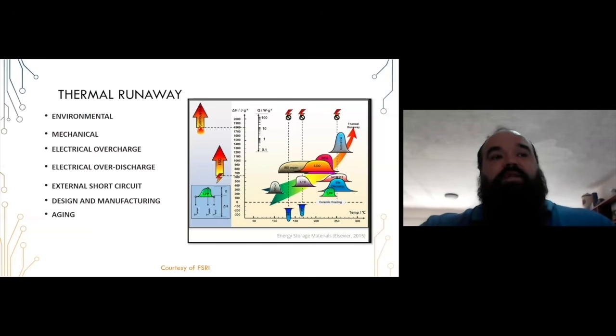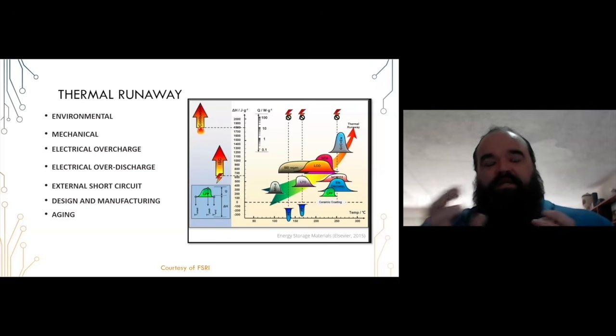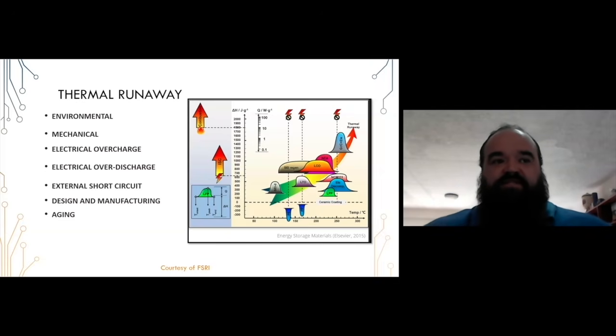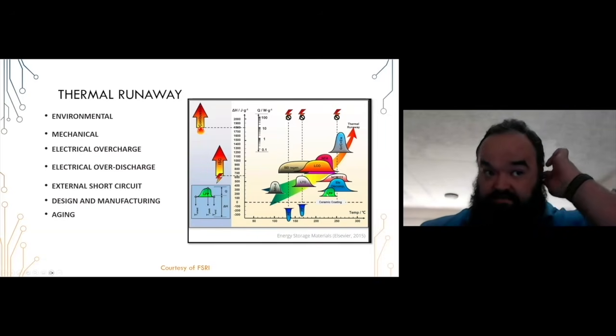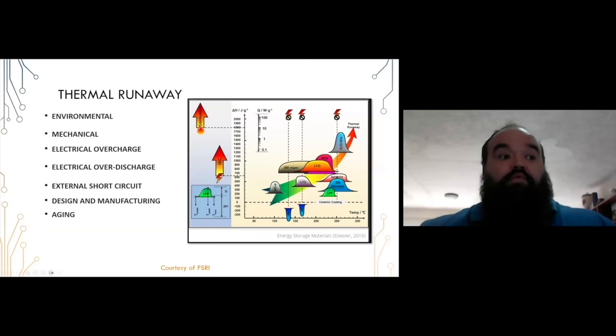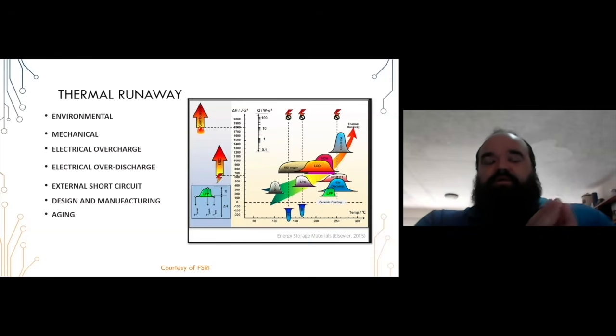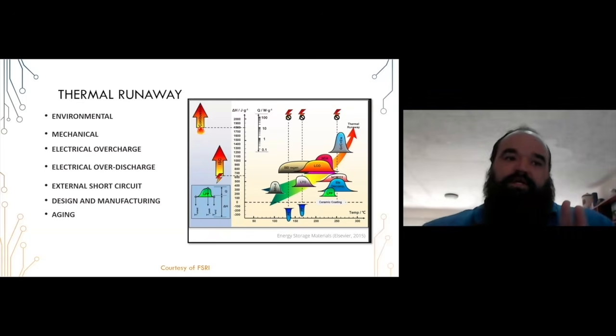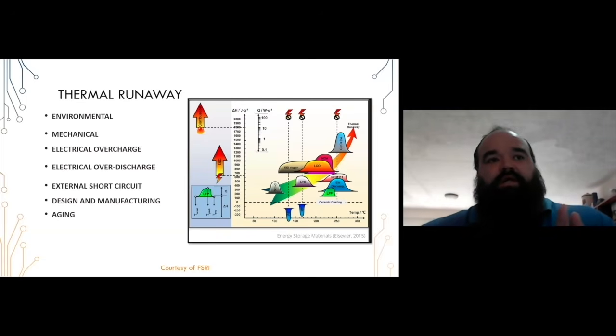Now, thermal runaway is typically caused by a couple of various techniques, and thermal runaway variances differ on the makeup of the battery. Our most common type of battery is lithium iron phosphate, aka LFP, which will go through thermal runaway in a very short bandwidth, between 200 odd degrees to about 250 odd degrees, and it would go into that thermal runaway, burn out its energy, and then go away.